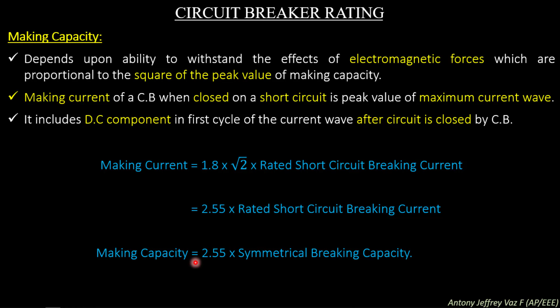The making capacity will include the DC component in the first cycle of the current wave after the circuit is closed. Here you can see making capacity will be equal to 1.8 into root 2 into rated short circuit breaking current. This is the rated breaking current. We need to multiply it by 1.8 into root 2. While multiplying this, we get the making current. To simplify, multiplying these two values gives 2.55 into rated short circuit breaking current. So the complete making capacity will be equal to 2.55 into symmetrical breaking capacity.